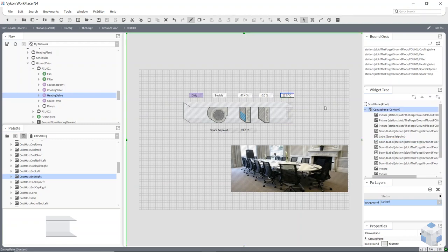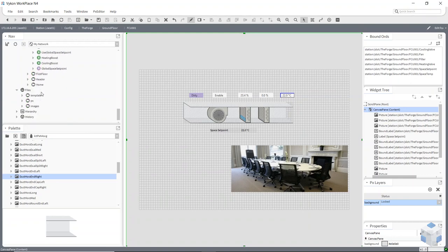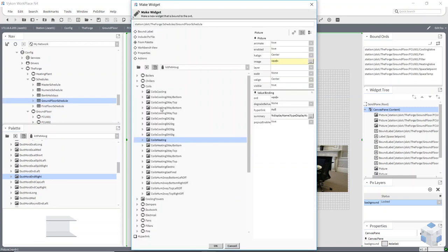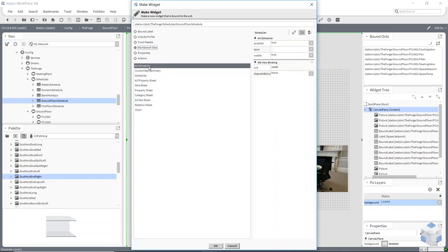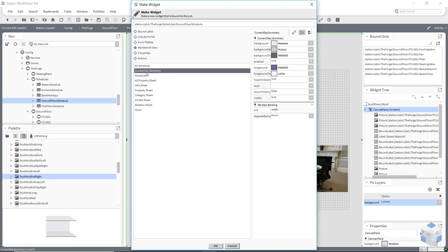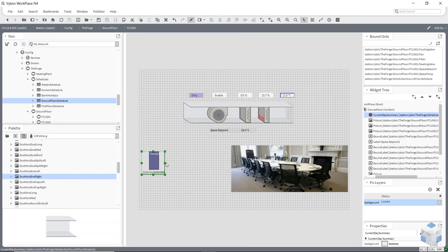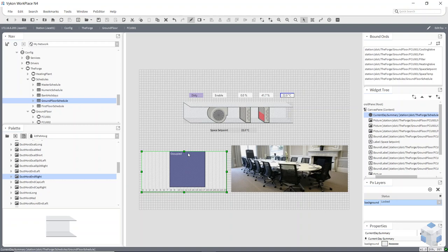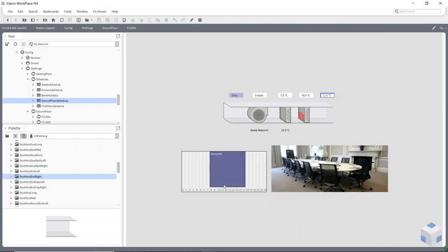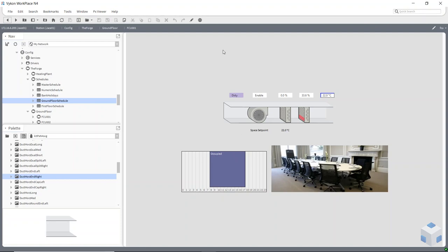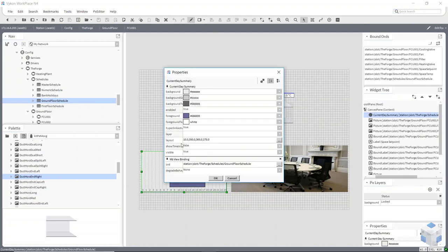Another thing you might want to add is a schedule. If I go to my ground floor schedule and add it using Workbench View, you've got an AX Schedule which shows the whole schedule, or a Current Day Summary. You can have that on your page using the Workbench View option. When I click on it, it's actually a hyperlink to that schedule. You can turn that off in the properties — there's an option called Hyperlink Active — if you don't want it to be a hyperlink.